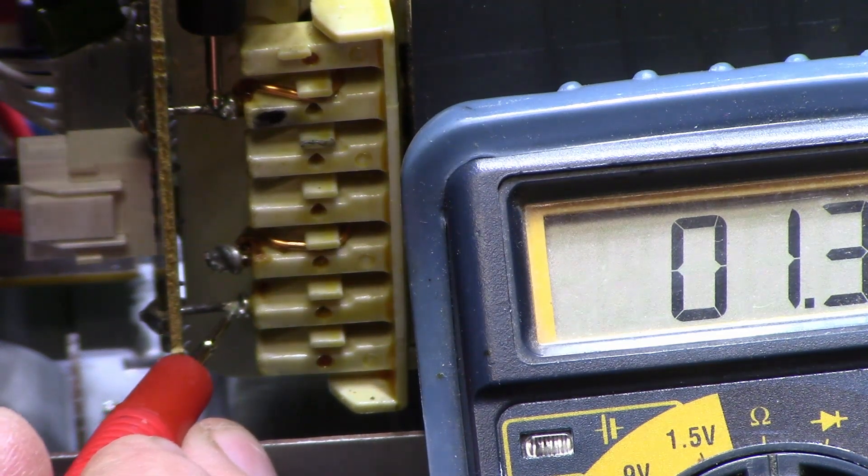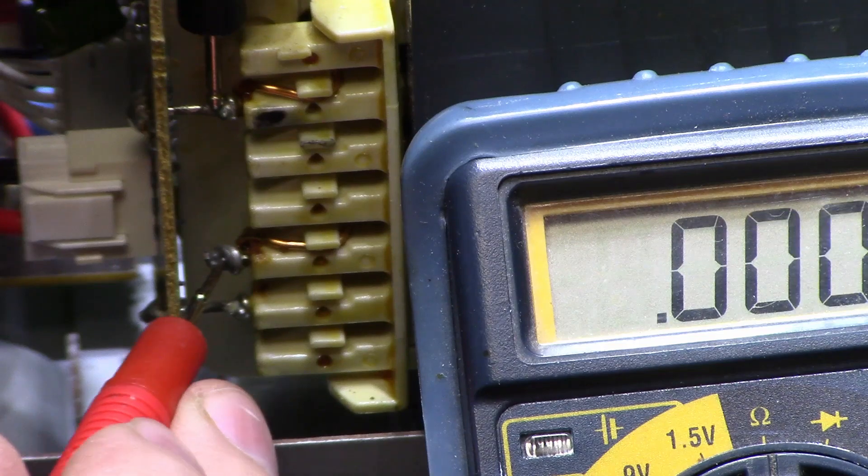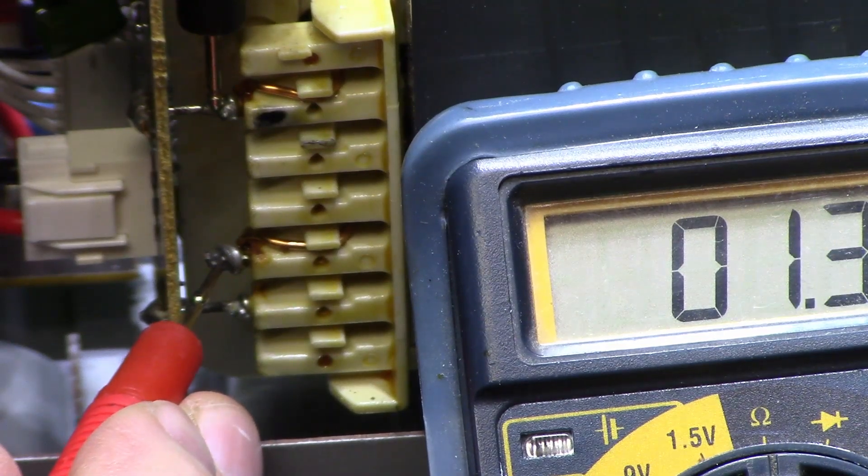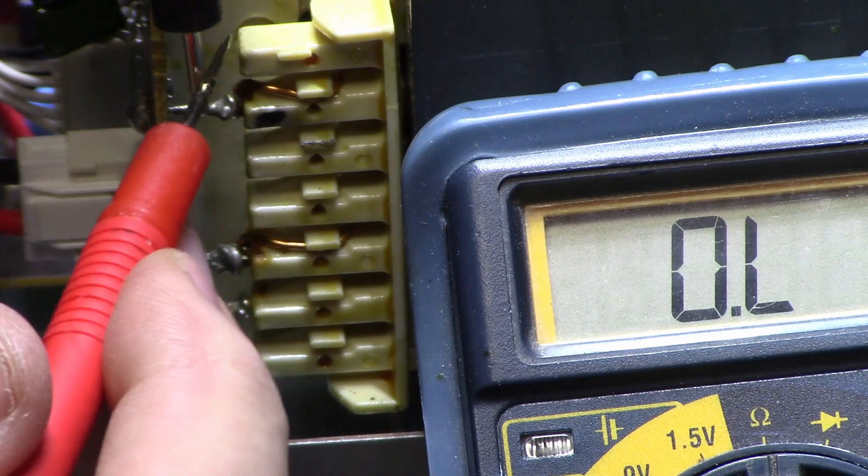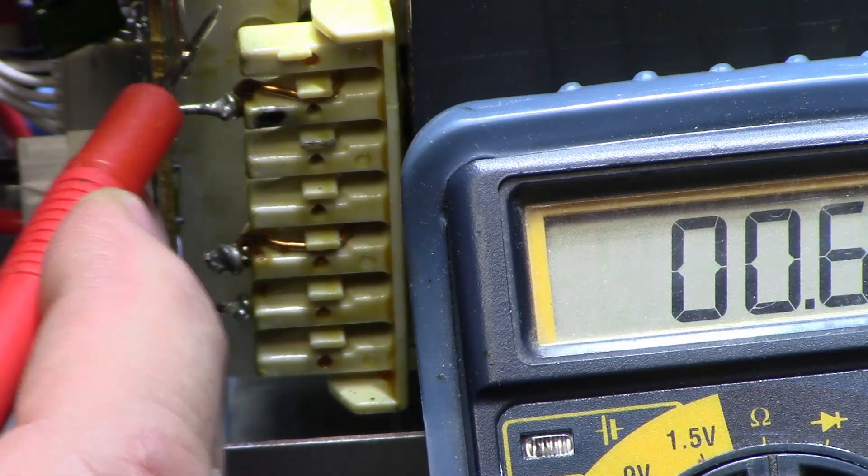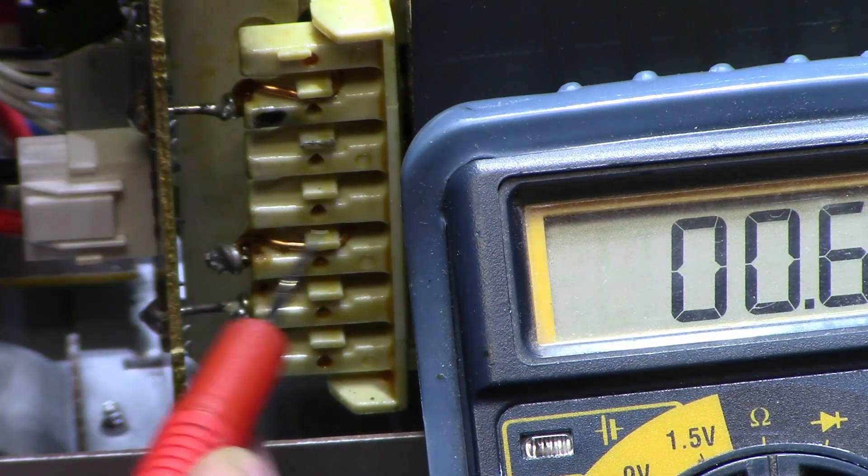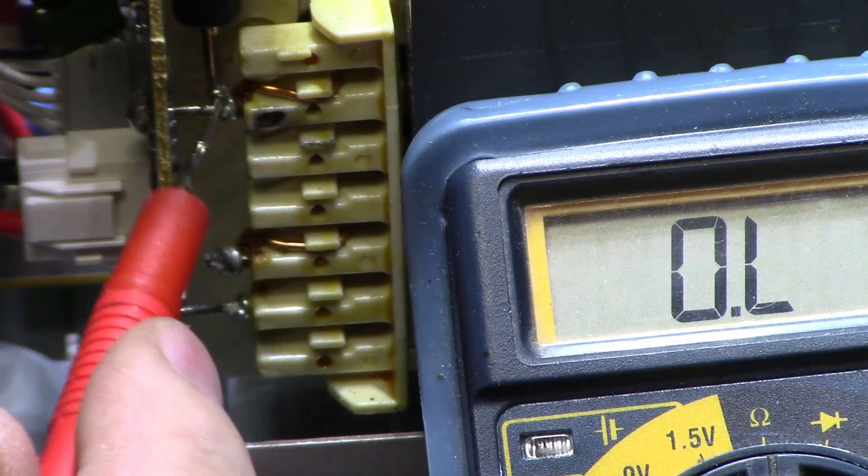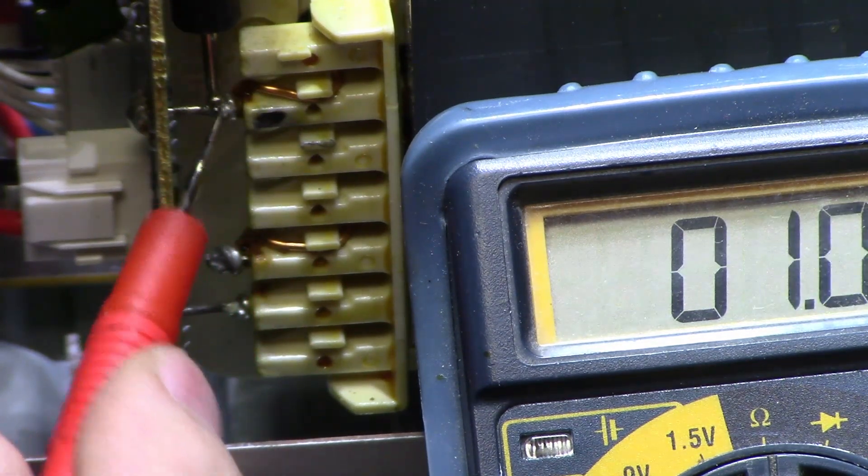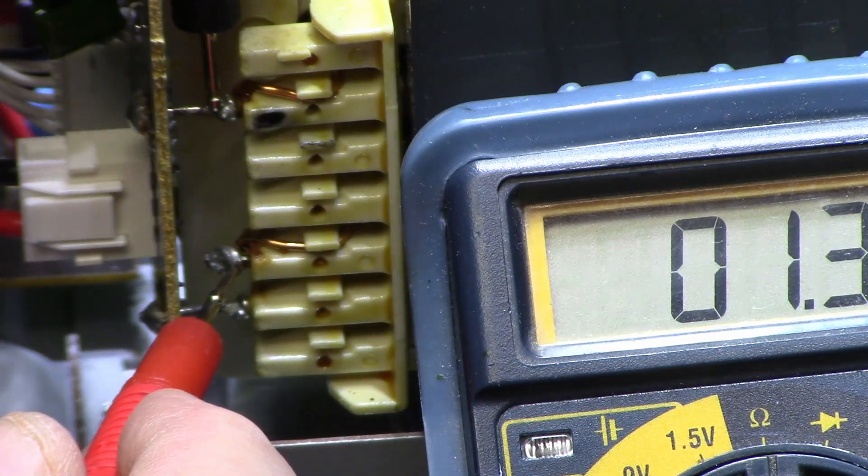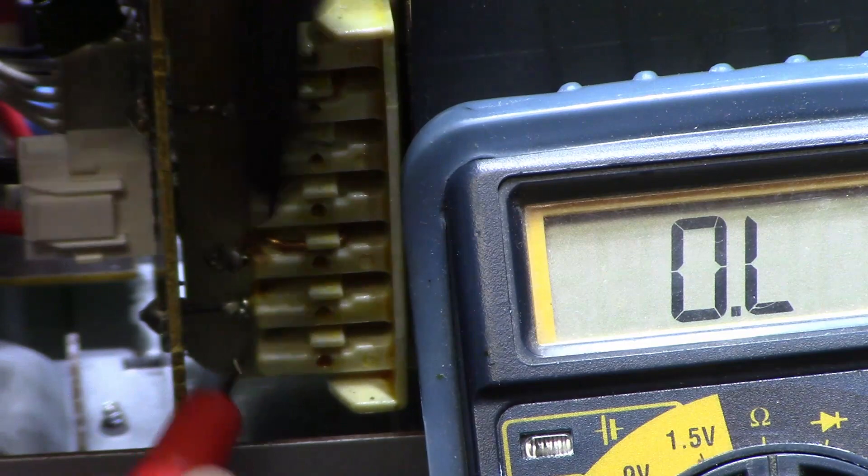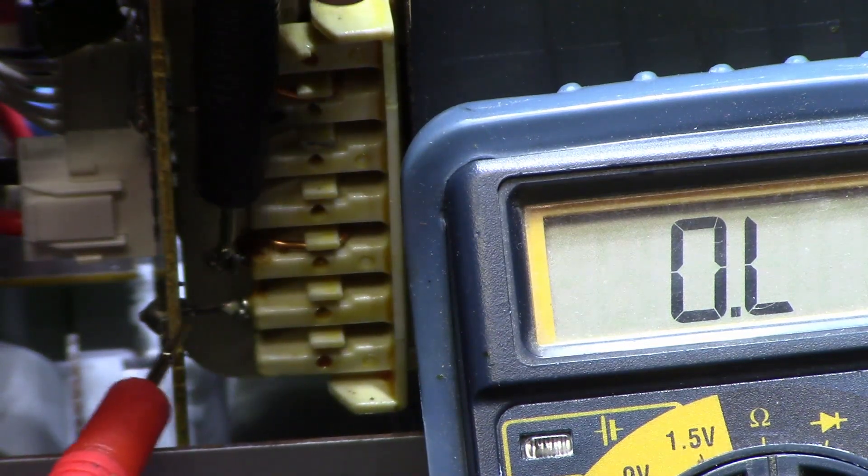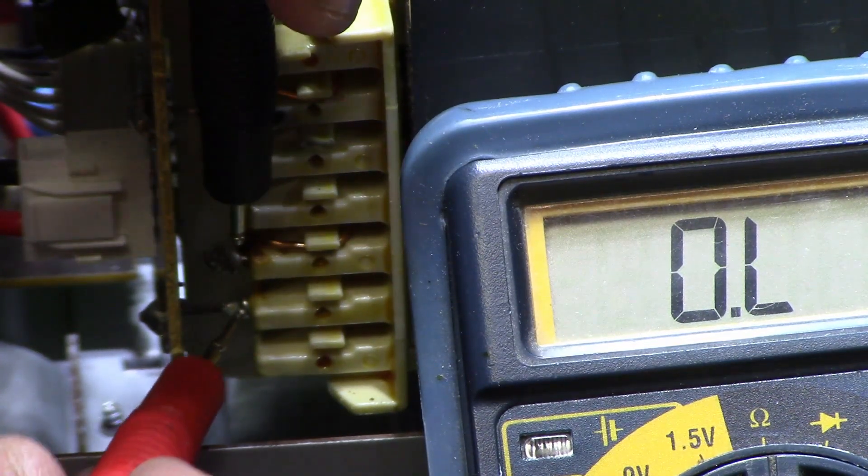1.3 ohms. Ohmmeter between here and here, this is your winding, 0.1, 1.3 ohms. And if I short, 0.6 or so, it's probably half that. But this one here, this pin here and this pin here is your winding. You can check for continuity on that.